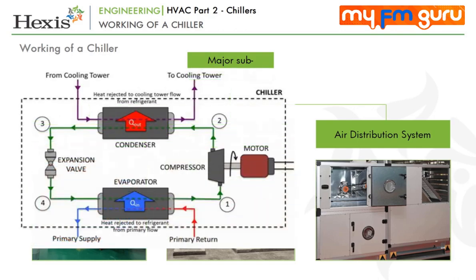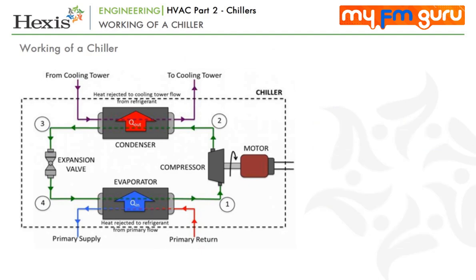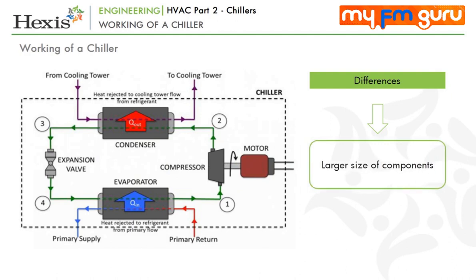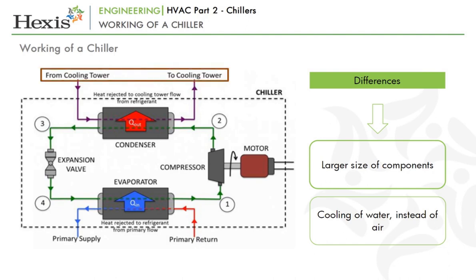In the case of a water-cooled chiller, another component — the condenser cooling system — comes into play. In this module, we will learn about water-related systems, and in the next module we will cover air handling systems. The chiller itself operates in accordance with the regular vapour compression cycle or vapour absorption cycle as described in the earlier module. It comprises a compressor, condenser, evaporator and expansion valve. However, there are two main differences: first, the size of the components is much larger; and second, instead of the refrigerant cooling the air in the evaporator, it is now cooling water. The diagram also shows a connection going to the cooling tower, which means it represents a water-cooled chiller.